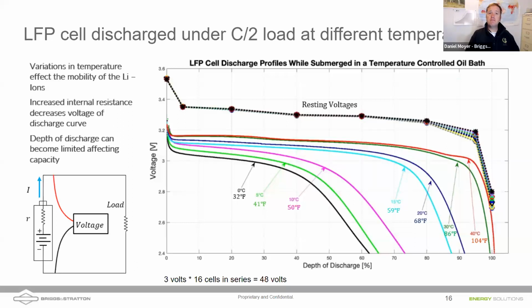The other point to make quickly is that when you're charging and discharging batteries, they typically heat themselves up and get to warmer temperatures while cycling. But in really cold environmental temperatures, if the interior of the battery is cold, this plays a bigger role in when the inverter kicks on and off, if the decision to run a charging cycle is based only on voltage.